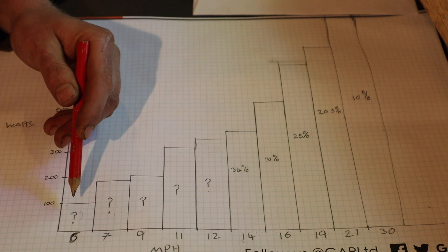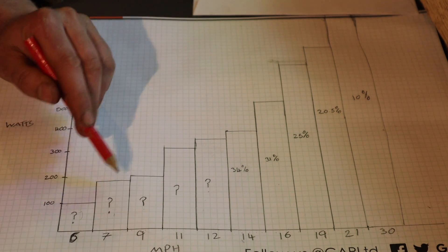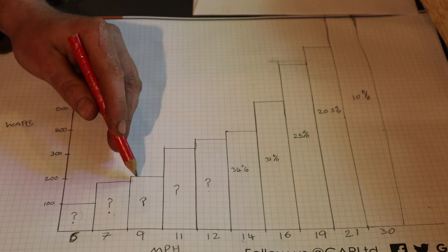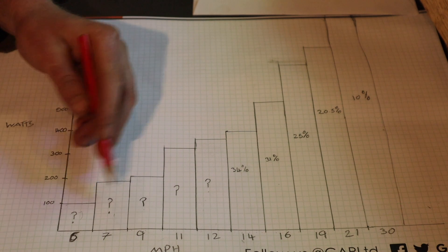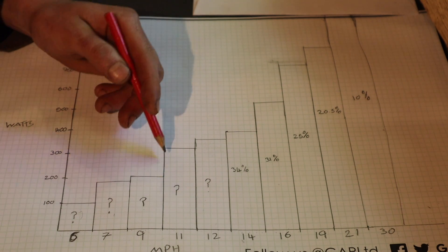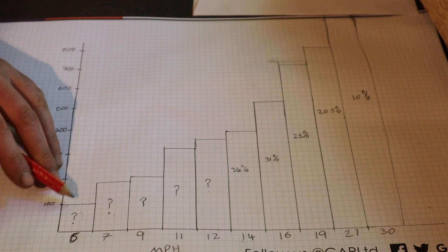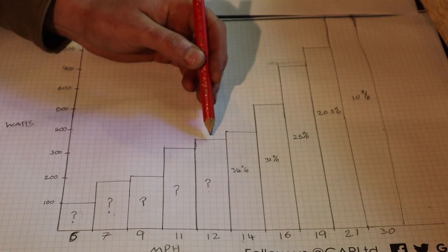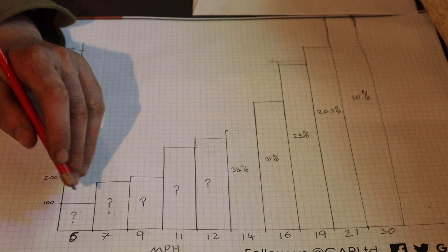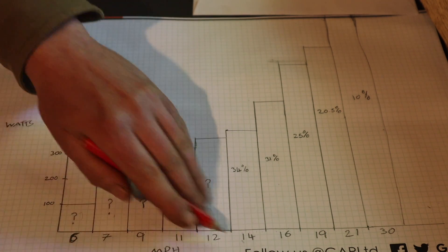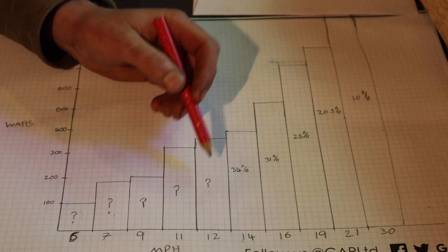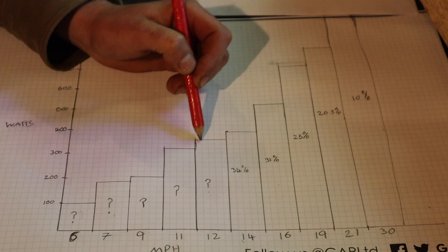So I don't think that they're wrong as such. I think the gain in them is fairly accurate because it looks quite right, because it's lower down we've got this lower output in the lower ranges as it's overcoming the losses in the turbine and in the blades and whatever else. And then it starts to overcome those losses and make more power and get into a more efficient range. So I think the way they're staggered looks quite accurate, I think they'd all just be a little bit further down. I think we were behind them a little bit with the meter. So yeah, on the side here we've got hundreds of watts, along the bottom obviously miles per hour wind speed. So yeah these first ones, can't give you an efficiency of them and I don't think those readings are accurate. Those readings would all be stepped down quite a bit.